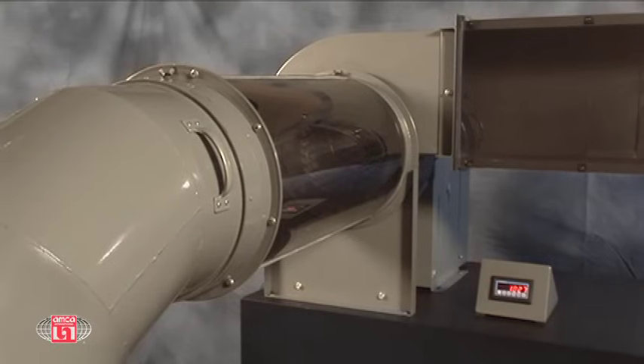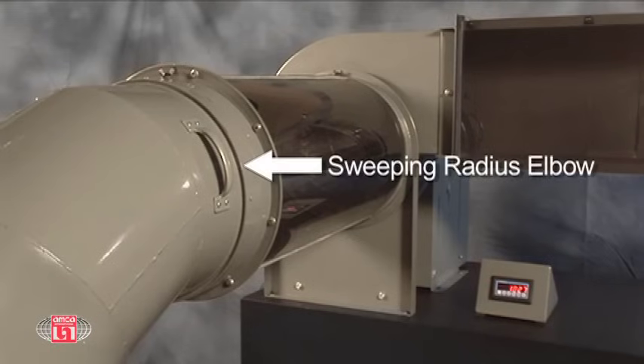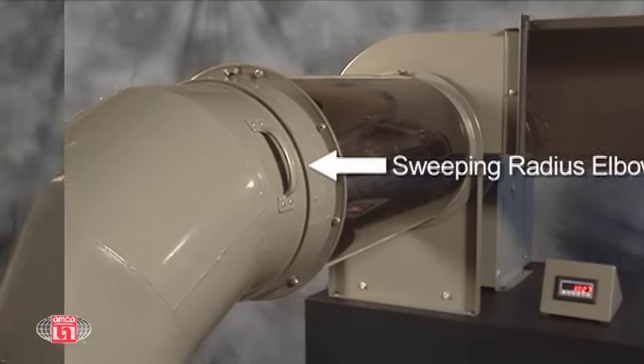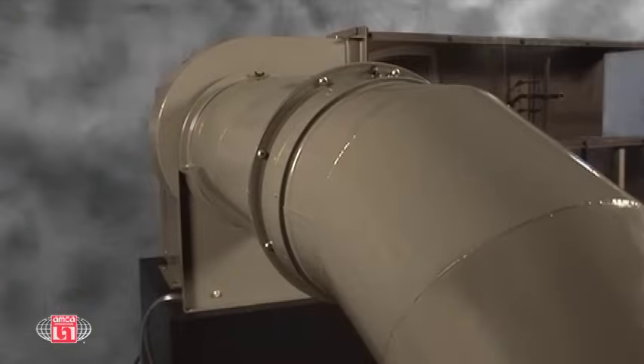A good rule of thumb is that elbows near the fan's inlet should be radiused and include turning vanes when located within 3 duct diameters upstream of the fan, recognizing that mitered elbows, with or without turning vanes, can cause system effect even when located up to 5 duct diameters upstream. The second major impact involves proper fan outlet design.